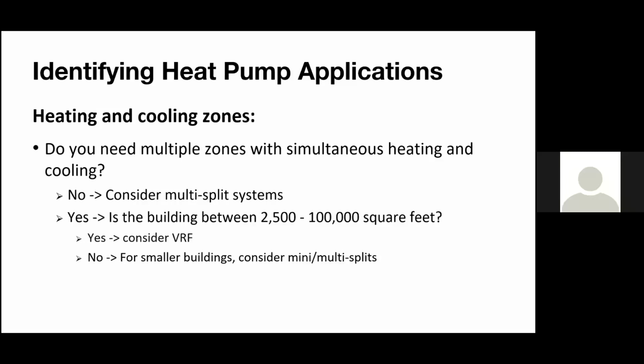If you're dealing with a larger building, maybe 2,500 to 100,000 square foot building, maybe it's an office space, that would be a little bit more useful for applying VRF technology, because you might have a conference room, right, with 15, 20 people in it, right? It's maybe close to the dead of winter, right? And you might need some cooling out of that, whereas all the exterior office spaces need heating. So just something to think about.